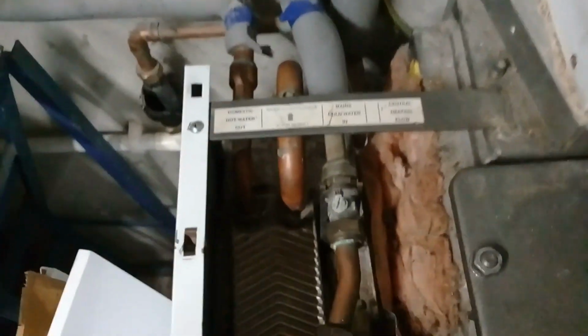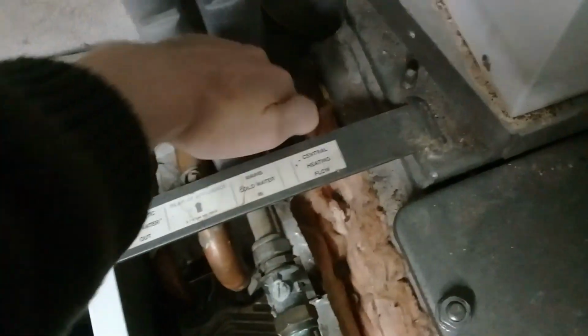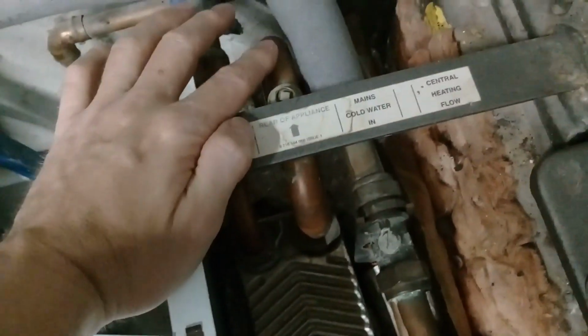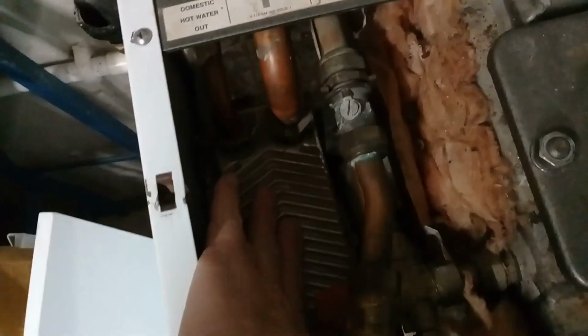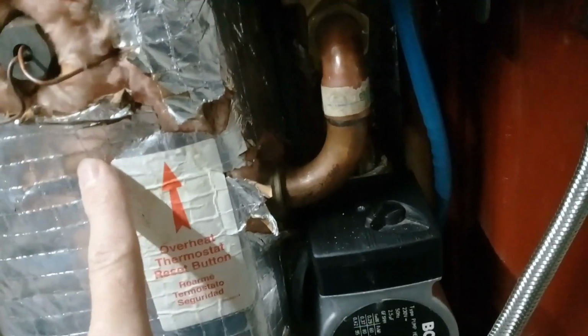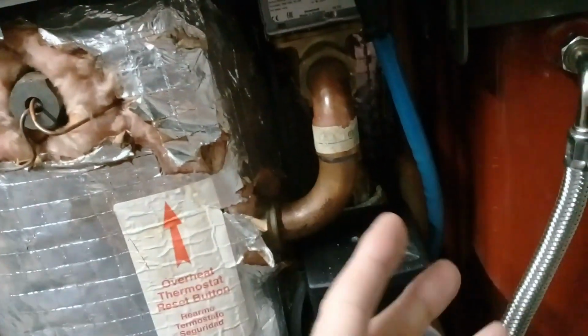So the other symptom I had was at the back of the boiler we've got these pipes. Touching the central heating flow pipe with the central heating on, again, because there's no flow, this was lukewarm. This pipe for the heating of the water was red hot. This heat exchanger, plate exchanger for the hot water, was red hot. Hot water seemed to be coming back here, coming through here, and eventually also coming through here from the hot store. So it looked like no circulation, hot water naturally being pushed through this heat store.